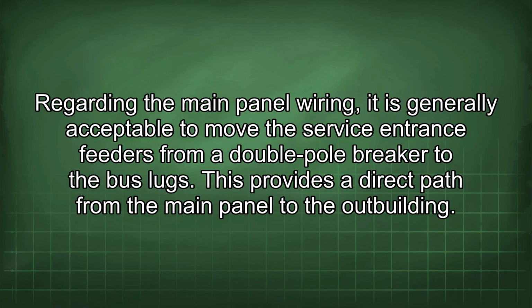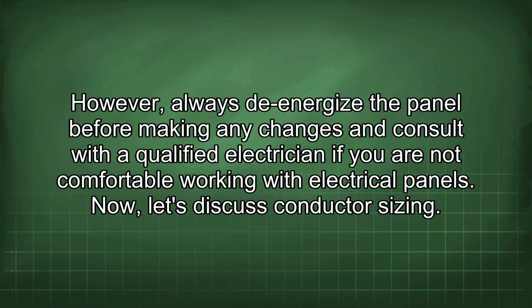Regarding the main panel wiring, it is generally acceptable to move the service entrance feeders from a double pole breaker to the bus lugs. This provides a direct path from the main panel to the outbuilding. However, always de-energize the panel before making any changes and consult with a qualified electrician if you are not comfortable working with electrical panels. Now let's discuss conductor sizing.